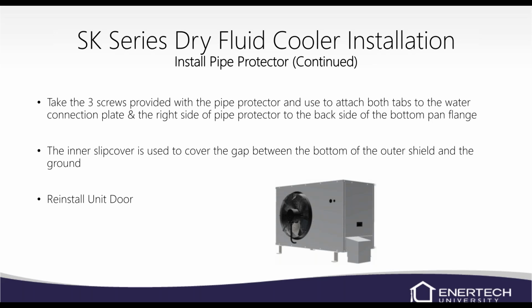Make sure you take the 3 more screws provided in the bag with all the feet and all that, and use them to attach both tabs to the water connection plate and the right side of the pipe protector. I know it sounds a little bit more difficult. Once you get this unit and get that box out there, it doesn't really take instructions to get it on there. It's pretty self-explanatory. So the inner slip cover is used to cover the gap between the bottom of the outer shield and the ground. After you get that pipe shield on, you may want to leave the door off so you can set up some dip switches, but once you're done with that, don't forget to put the door back on.